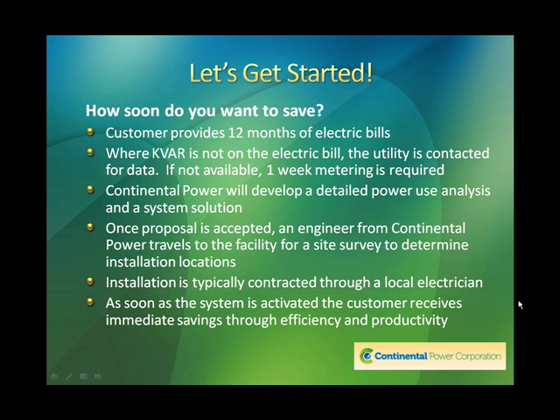I'll ask a question. How soon do you want to save? Well, here's what we need. The customer provides 12 months of electric bills. Where KVAR is not on the electric bill, the utility is typically contacted for data. If not available, typically we try and put a meter on, a data acquisition meter. Fluke makes a meter that is especially useful for this, the Fluke 1735, and meter that facility for 1 week to get the information we need.